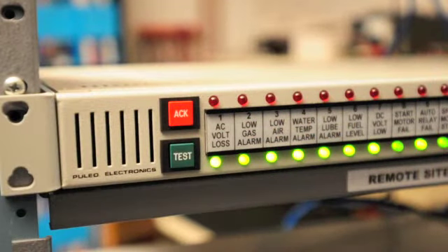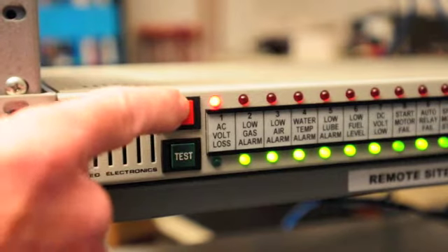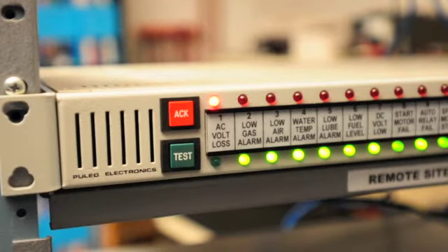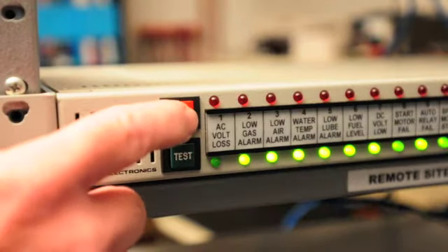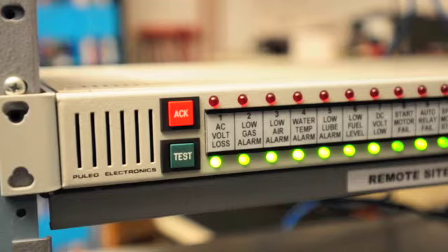Each alarm point has 2 LEDs, a green and a red. When an alarm occurs, it goes from a solid green to a flashing red, and you get the SonAlert to sound. By pressing the acknowledge button, the audible is silenced and you get a solid red. When the alarm clears, it goes to a flashing green, the sound is heard again, and the acknowledge button turns everything to a steady green and silences the audible.